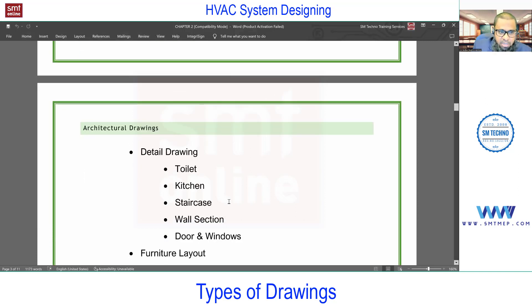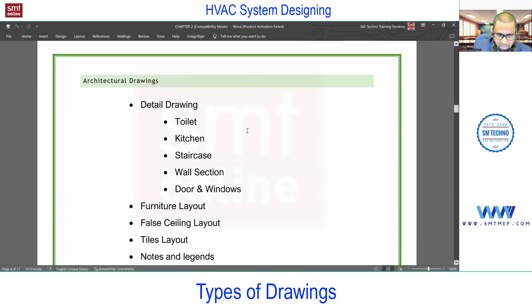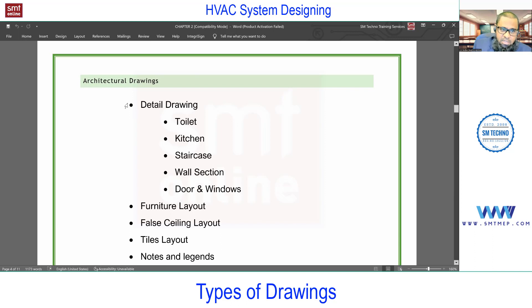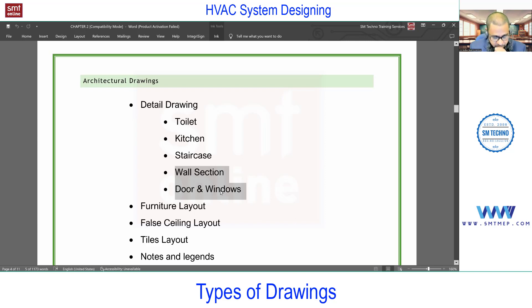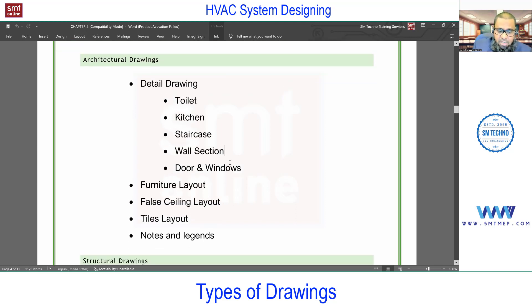Next, as an engineer you should have knowledge of architectural drawings and different service drawings, because without extracting information from architectural drawings you cannot deal with any service. In architectural drawings you'll find detail drawings for toilets, kitchens, staircases, wall sections, doors, and windows. The wall section is important for HVAC engineers to extract the material used in wall construction, which is needed to find the U-value — the overall coefficient of heat transfer — since actual heat gain depends on U-value and thermal resistance of materials.